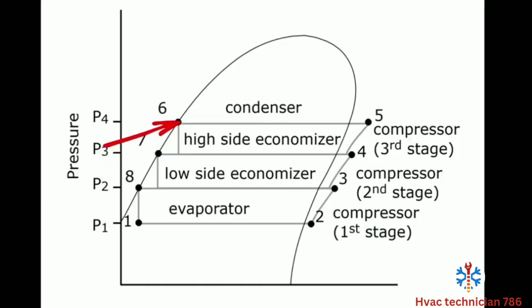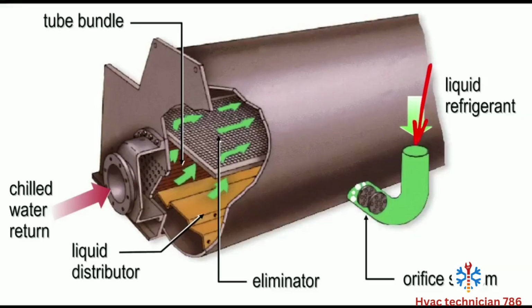And you can see the difference if we just go straight from this point number 6 straight down and over versus where we land at number 1 over here. There's a lot of enthalpy reduced on that refrigerant, which really helps increase our effectiveness of our refrigerant, while also reducing total load on the compressor. Leaving our economizer at a medium pressure liquid refrigerant coming into our orifice plates, there's a dual stack here. This comes back into load control. So that's not the scope of today's video, but essentially higher load, lower load will affect how these flash off.